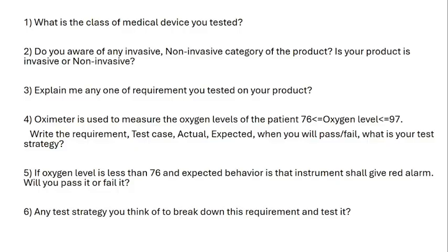Then the third question is, explain any requirement you tested on your product. Here I am using an electrosurgical generator. It has a monopolar port and two modes, cut and coag. We use the monopolar instrument to cut the cancer lesions, or coag means we can seal the cancer lesions. So I said the requirement is that in cut mode the maximum power shall be 150, and for coag mode the maximum power should be 200.